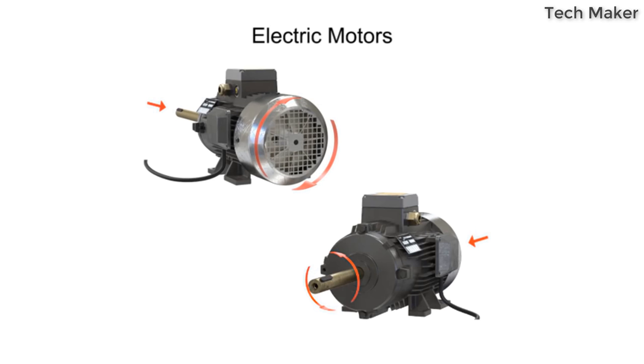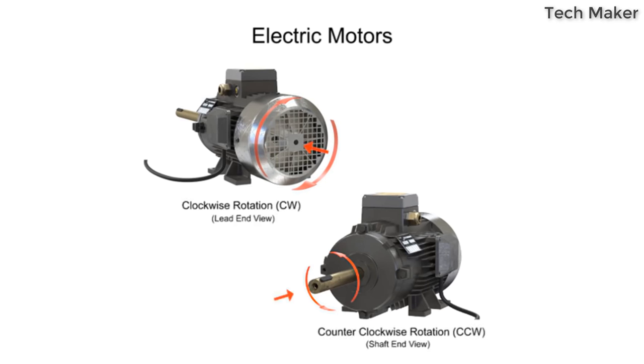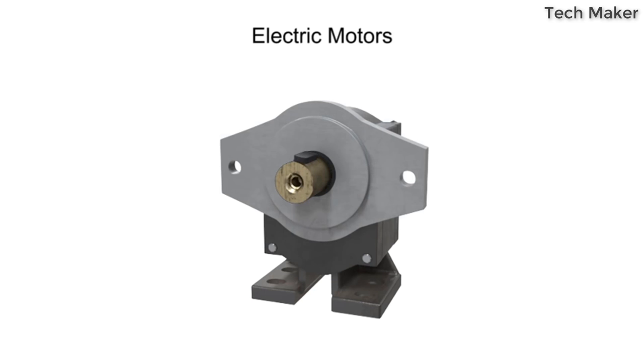In general, for most electric motors, rotation is specified as clockwise or counterclockwise when viewed from the opposite end of the shaft. This is sometimes called the lead end since the electrical wires or leads typically connect on this end. By contrast, the rotational direction for hydraulic pumps is specified as clockwise or counterclockwise rotation when viewed from the shaft end.